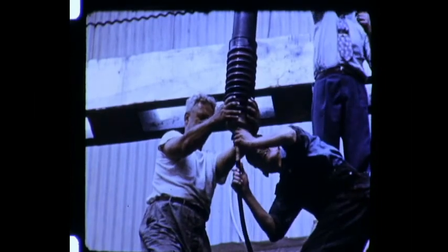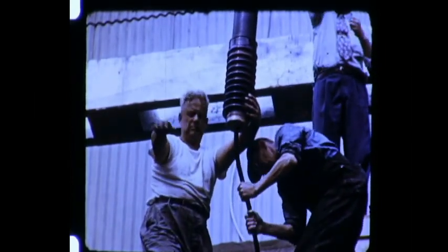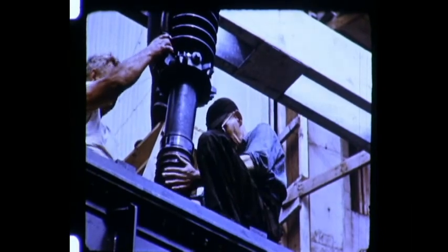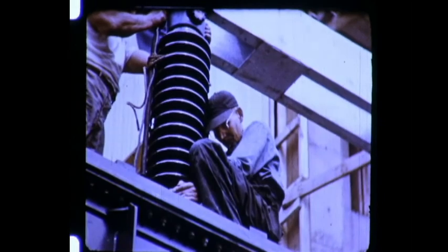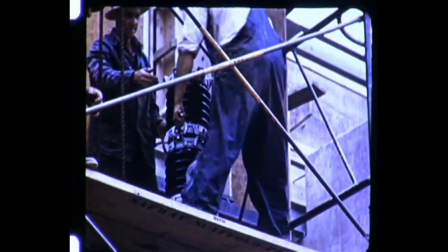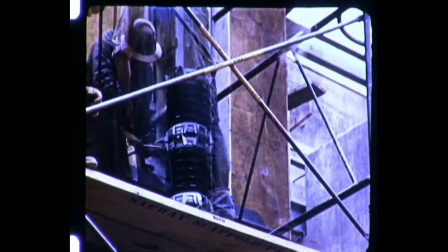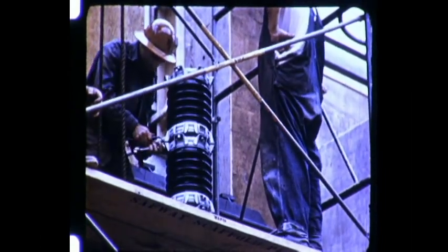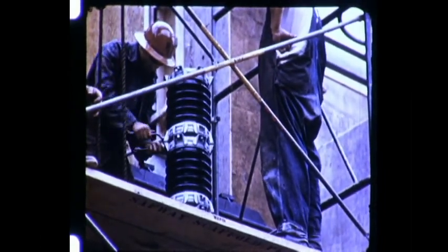A guide wire is again used to help pull the high voltage lead up and through the center tube of the high voltage bushing. With the bushings in place, there remains but the job of mounting and assembling the lightning arresters and the remotely located water coolers, the final steps in installing 145,000 kVA of modern power transformer.